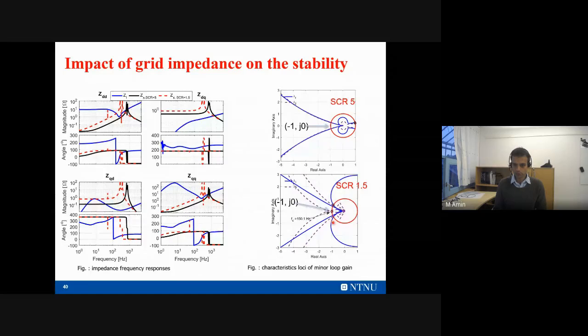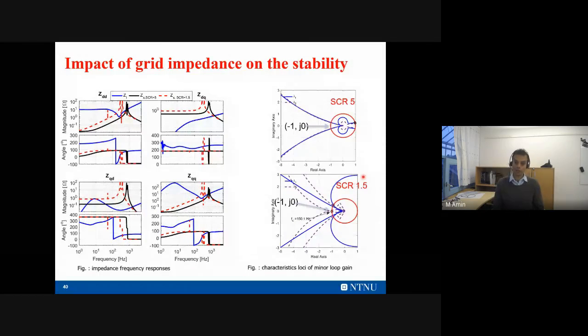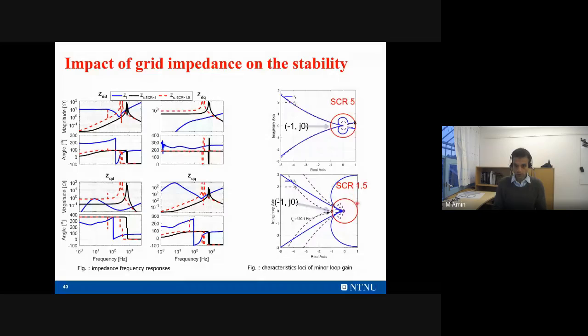But when we reduce the short circuit ratio of the grid, making it weak by increasing the impedance or having a very long transmission line, we see that for a weak grid the system can become unstable. So now you can adjust different components of the system to make it stable analytically. Once it's stable analytically, you can verify it in simulation, and then proceed to real implementation of the system.